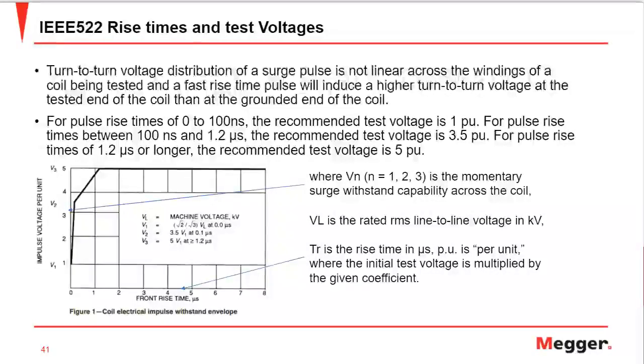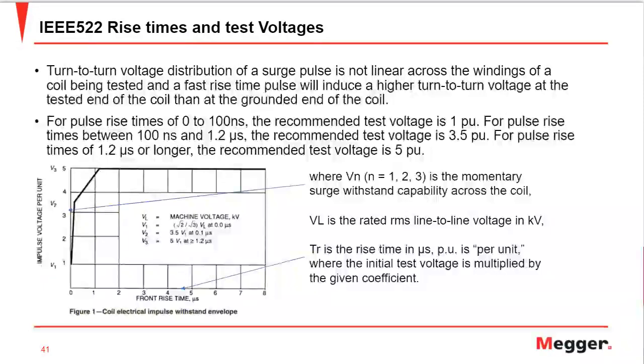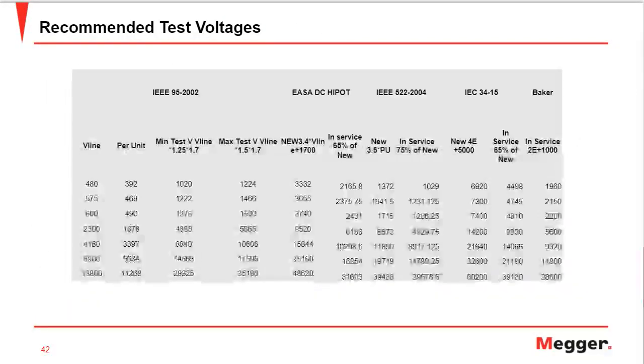So there are different standards which we've previously seen for DC high-pot. There are different standards for test voltages. There are different standards for surge test voltages as well. So we'll see combined test voltages for both high-pot and surge. There are various standards like previously mentioned, IEEE 95, there's EASA DC HiPot, and there's IEEE 522.